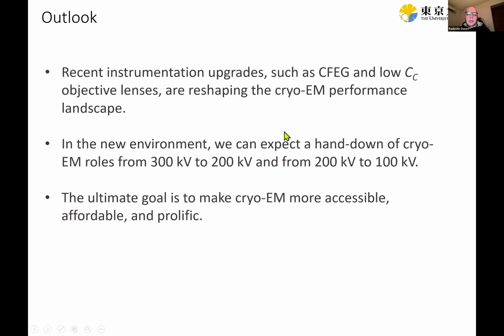And what could actually happen is a handing down of roles across the voltages. So for example, single particle analysis projects could move more to 200 kV high performance machines, with cold FEGs and narrow gap objective lenses, screening and initial data set collection from the 200 to 100 kV, and the 300 kV machines can provide more time for things like tomography and thicker samples. Of course, the ultimate goal is to make cryo-EM more accessible, affordable, and prolific in the end.